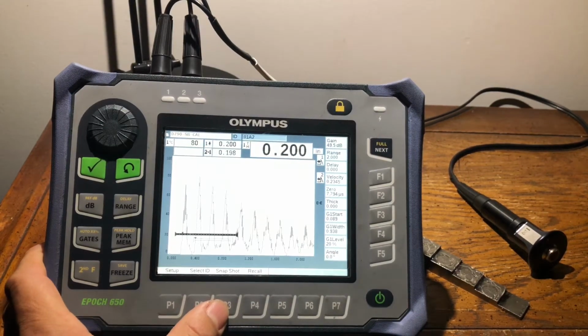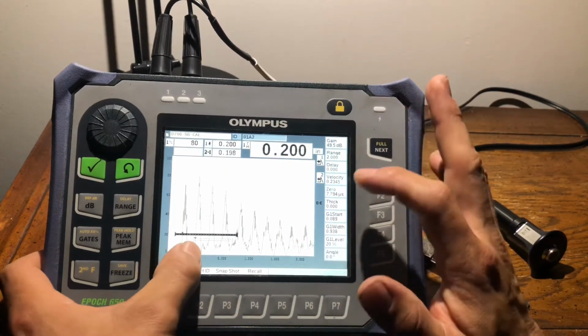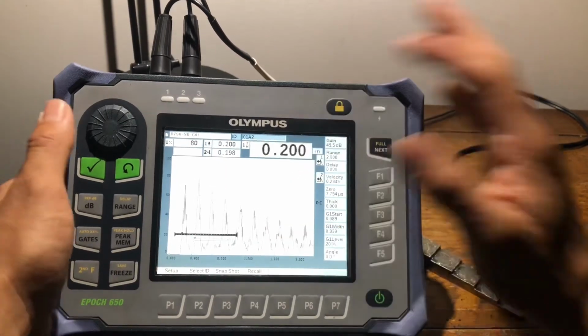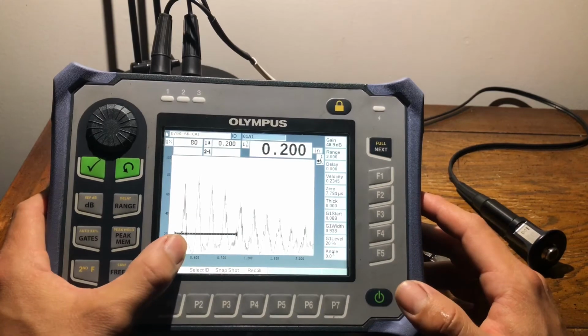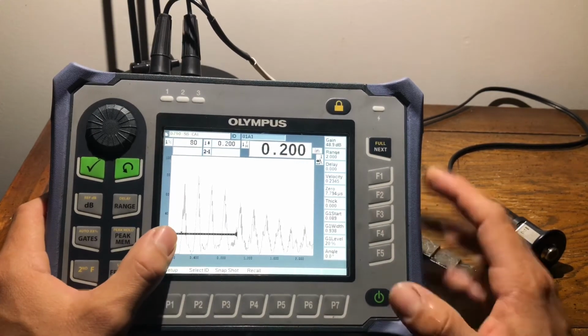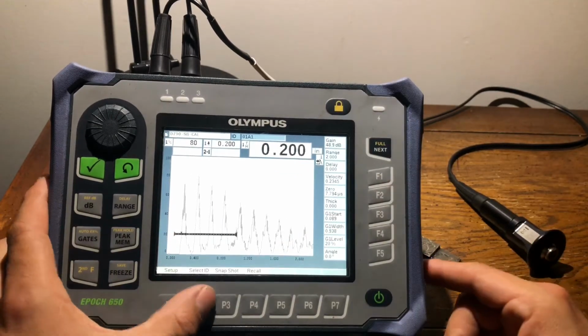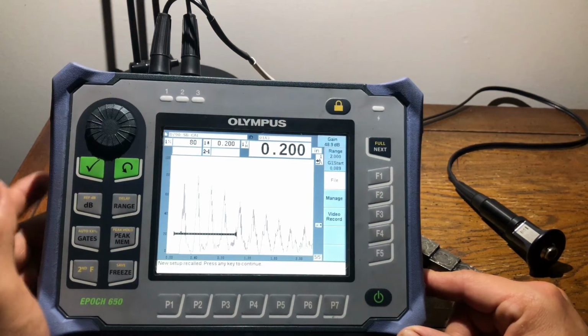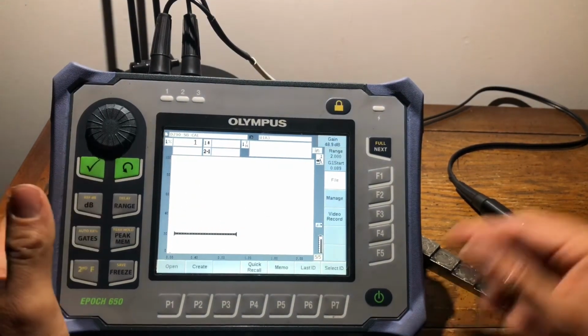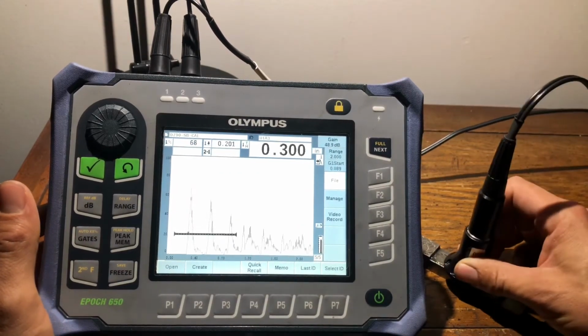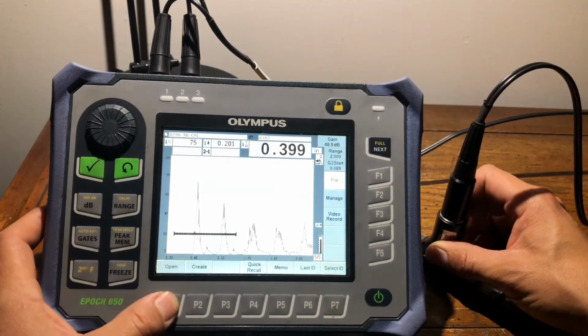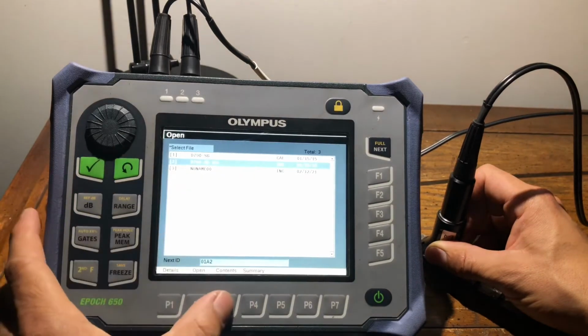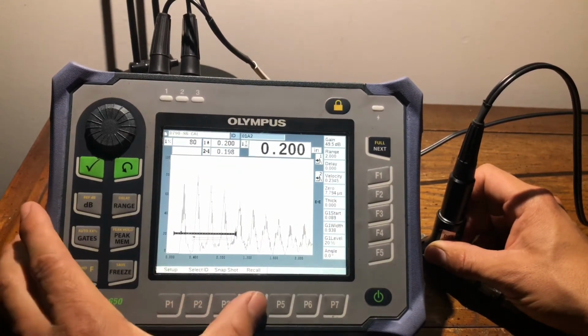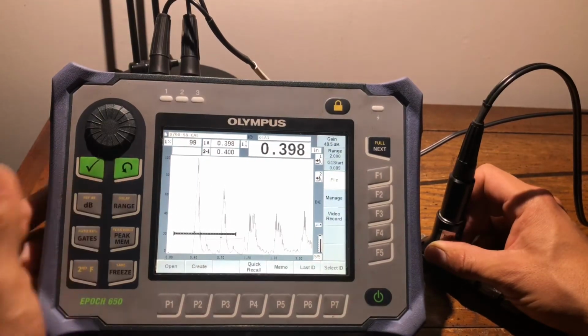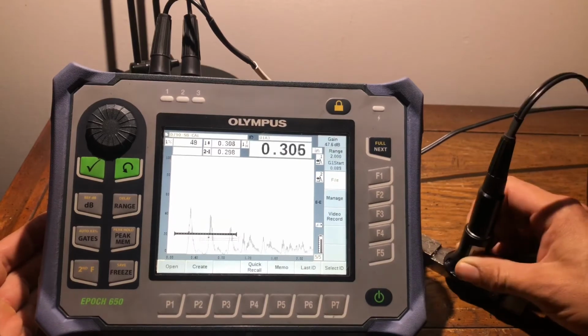On content, we will see that our calibration is saved here on the A2, 01A2. And if we scroll back, we will be able to see that our first file was saved here, our straight beam edge calibration. So we're gonna hit recall, and we're actually on the saved calibration. We're gonna hit any button and we should be back to where we had it originally. Now we're gonna go to open, and this is the file that we created. We're gonna go to content, and go to our second file just to see if it's saved. We're gonna hit recall, and this is the one where we had the 2 gates on edge, and there we are. You can see everything's back into place.